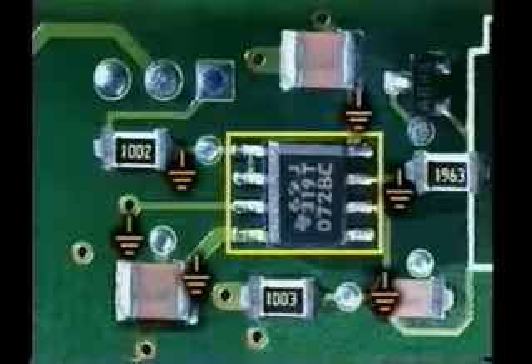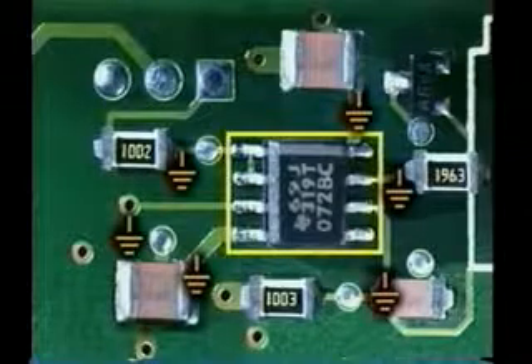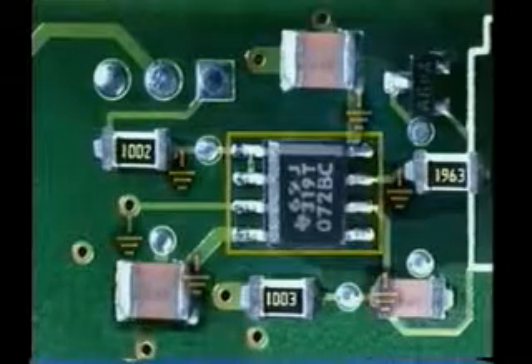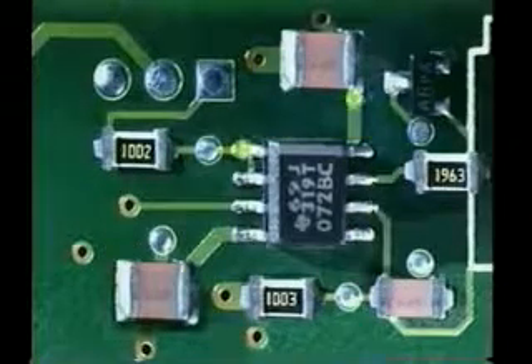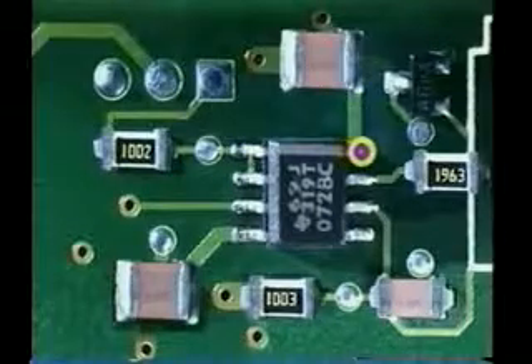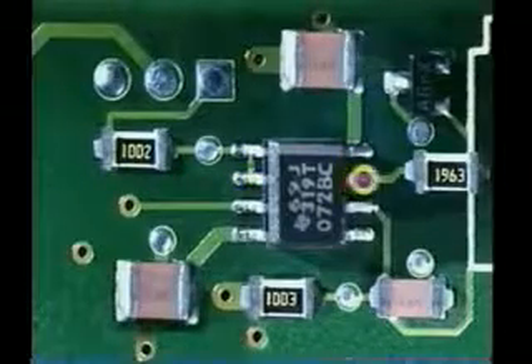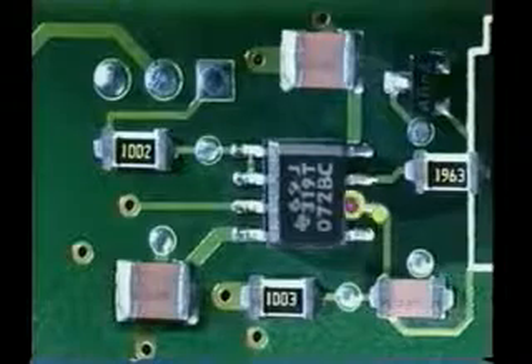Then a measurement is taken to make sure the component is working correctly. If the component wasn't guarded, you wouldn't know whether it was working properly. This is because there would be stray signals from other components that would change the measurement.